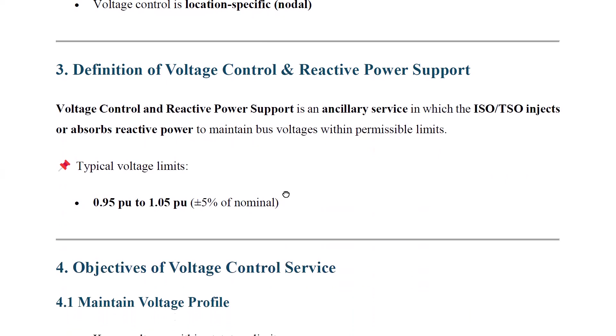Next comes the definition of voltage control and reactive power support. Voltage control and reactive power support is an ancillary service in which the independent system operator or transmission system operator injects or absorbs reactive power to maintain the bus voltages within the permissible limits. The typical voltage limits are plus or minus 5% of the nominal voltage. In per unit, it is 0.95 per unit to 1.05 per unit, because in power system calculations we deal with per unit.